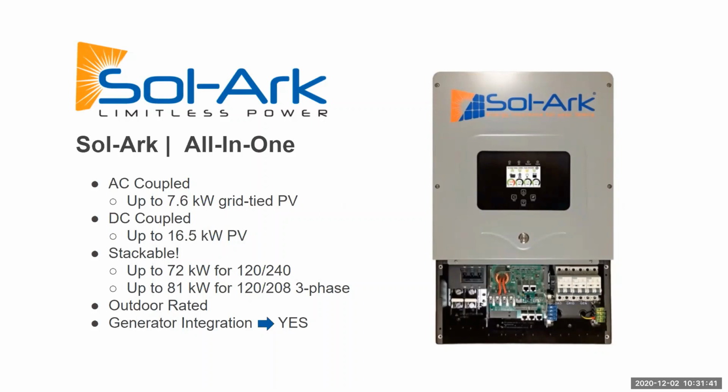The thing that is a little bit challenging and sometimes cumbersome is that battery bank sizing is custom. You really need to do it based on the needs of each consumer, because this isn't one size fits all. If you're running your microwave all day long, that's going to zap your battery bank really quickly. And if someone says, hey, I ran my microwave, but you didn't tell me I couldn't run my microwave, identifying an estimated time on these loads is paramount to understanding that. So rule of thumb would be double the kilowatts to get the kilowatt hours, but it's really better to do this on a system by system basis.